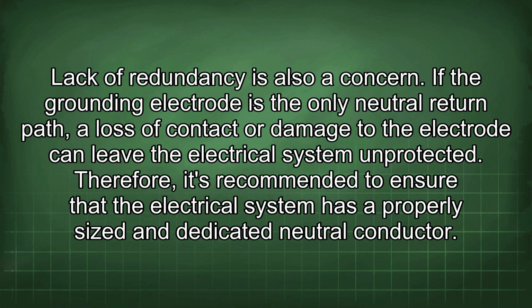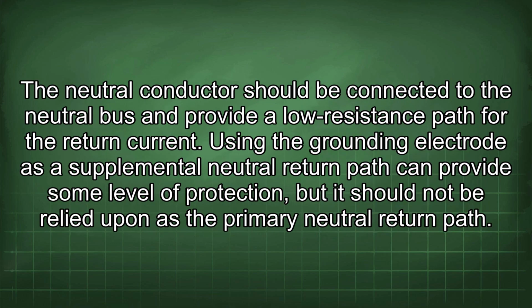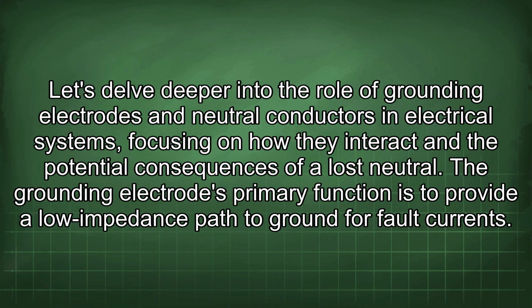Therefore, it's recommended to ensure that the electrical system has a properly sized and dedicated neutral conductor. The neutral conductor should be connected to the neutral bus and provide a low resistance path for the return current. Using the grounding electrode as a supplemental neutral return path can provide some level of protection, but it should not be relied upon as the primary neutral return path. Let's delve deeper into the role of grounding electrodes and neutral conductors in electrical systems, focusing on how they interact and the potential consequences of a lost neutral.